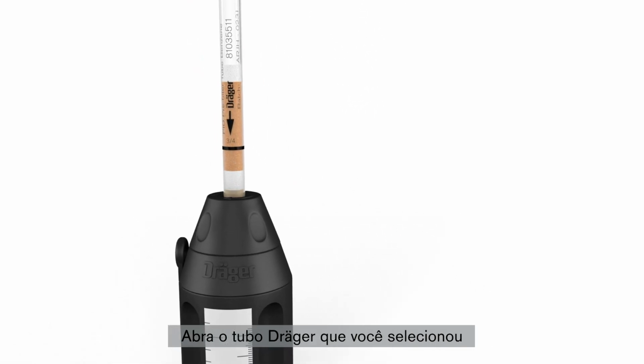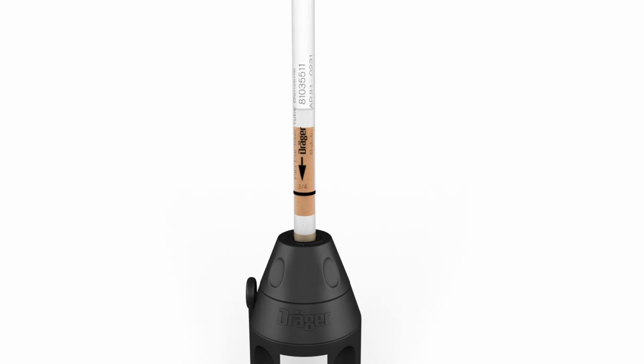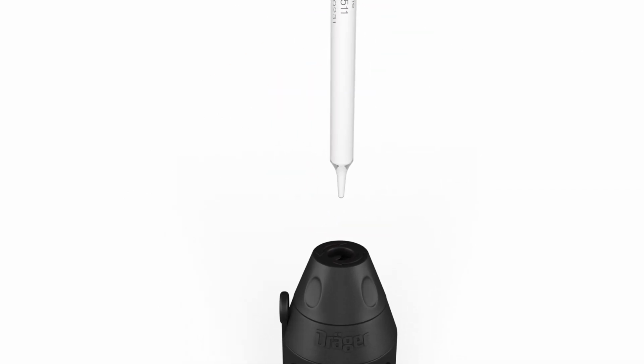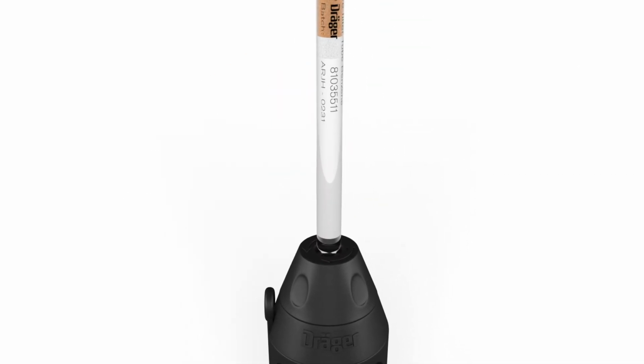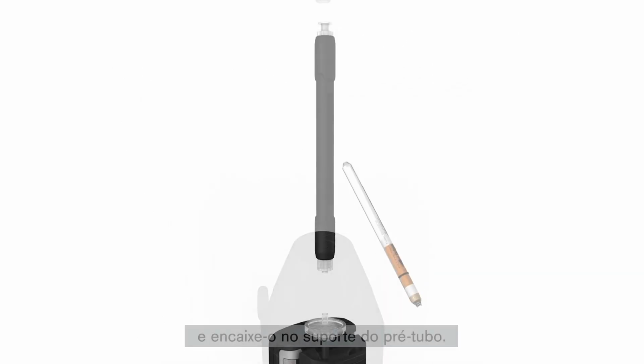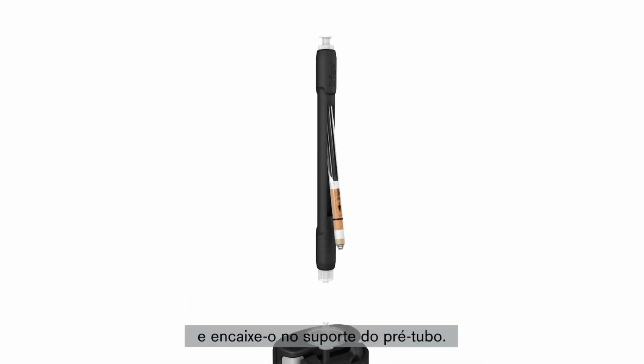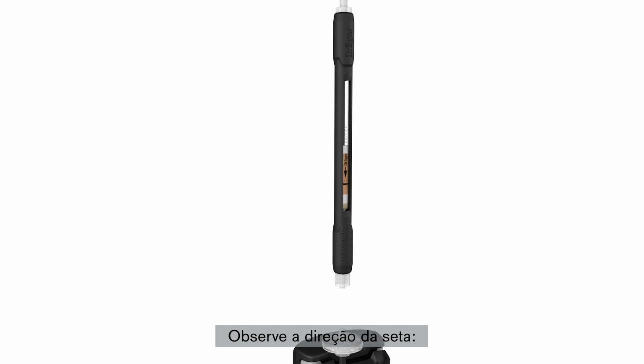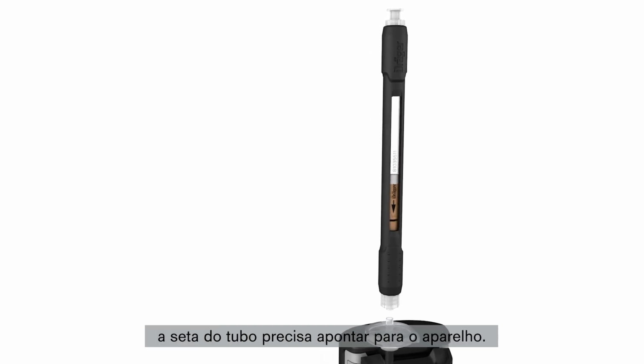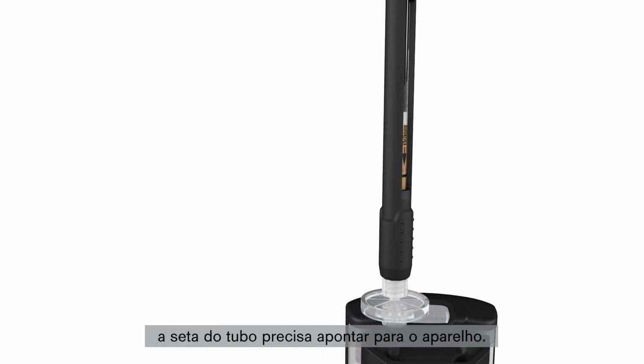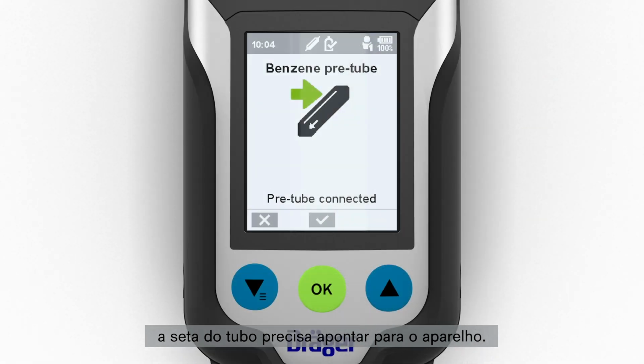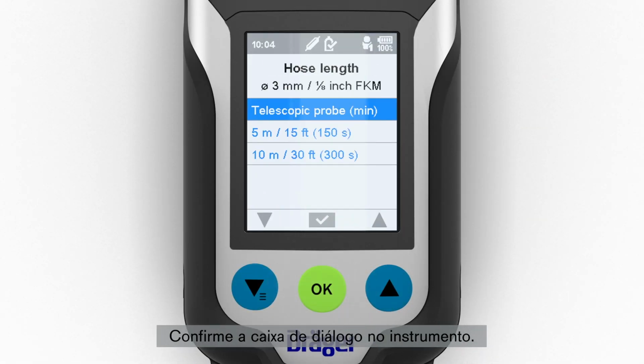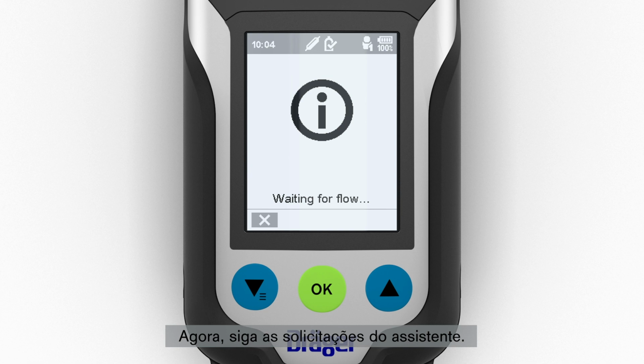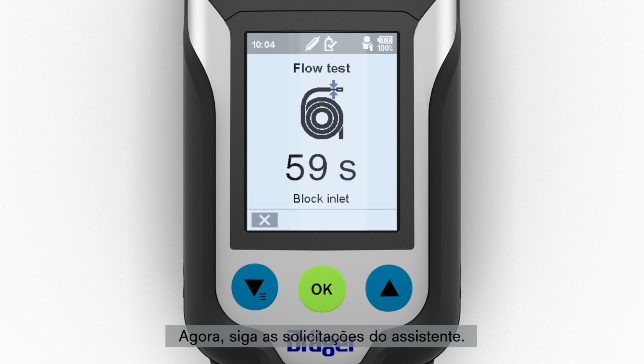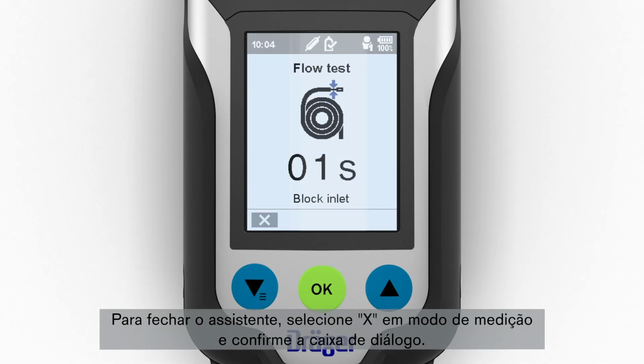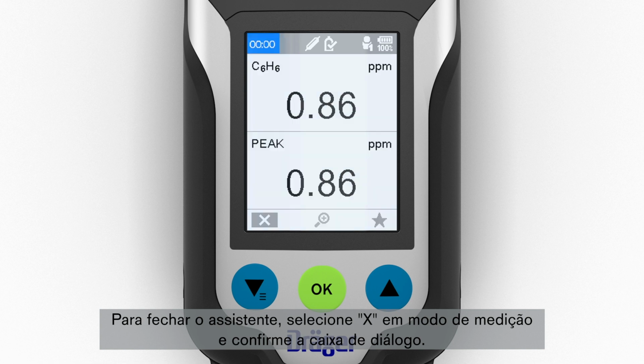Open the Dräger tube you have selected and fit it into the pre-tube holder. Pay attention to the direction of the arrow. The arrow on the tube must be pointing towards the device. Then confirm the dialog on the instrument. Now follow the prompts given by the wizard. To close the wizard, select the X symbol in measuring mode and then confirm the dialog.